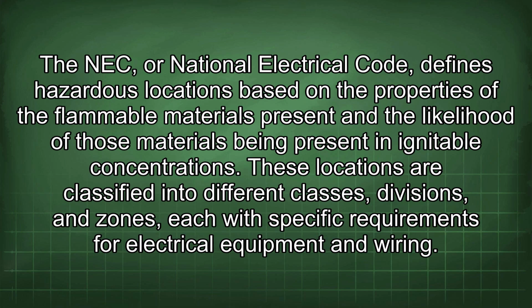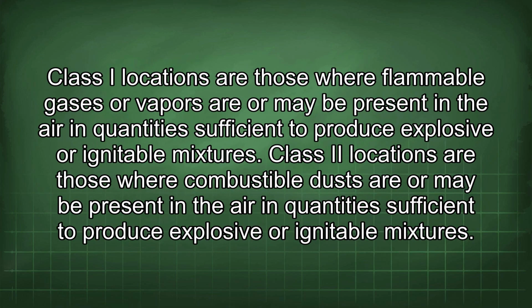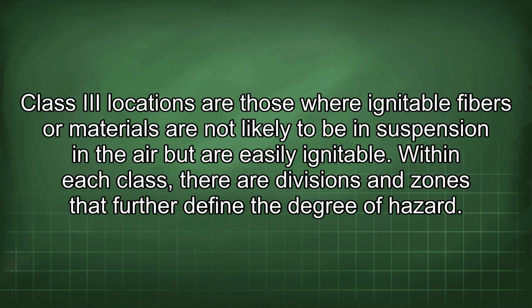These locations are classified into different classes, divisions, and zones, each with specific requirements for electrical equipment and wiring. Class I locations are those where flammable gases or vapors are or may be present in the air in quantities sufficient to produce explosive or ignitable mixtures. Class II locations are those where combustible dust is or may be present in the air in quantities sufficient to produce explosive or ignitable mixtures. Class III locations are those where ignitable fibers or materials are not likely to be in suspension in the air but are easily ignitable.